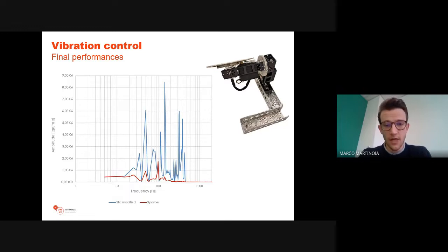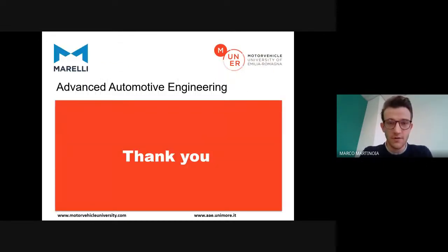As can be seen, in the range between 100 and 500 Hertz, the concerning part, as I said before, there has been a reduction of about 84% of the excitation perceived by the IPS. Therefore, we were able to obtain a system which is more compact, as I said before, and allowed us to perform the calibration in a smaller climatic test cell, and a system which is able to perform a quite good calibration, which doesn't take into account the problem coming from the excitations given by the climatic test cell. I would like to thank you, and if there are any questions.